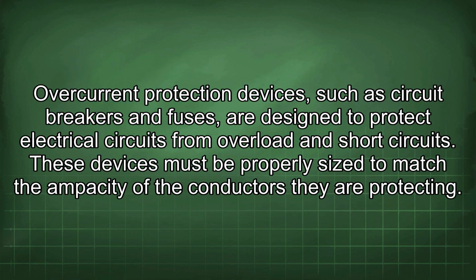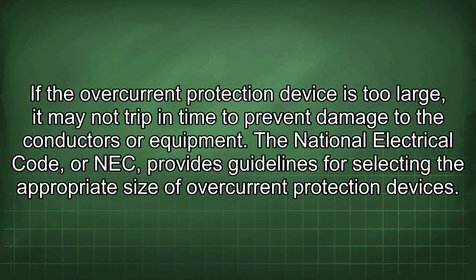Overcurrent protection devices, such as circuit breakers and fuses, are designed to protect electrical circuits from overload and short circuits. These devices must be properly sized to match the ampacity of the conductors they are protecting. If the overcurrent protection device is too large, it may not trip in time to prevent damage to the conductors or equipment. The NEC provides guidelines for selecting the appropriate size of overcurrent protection devices.